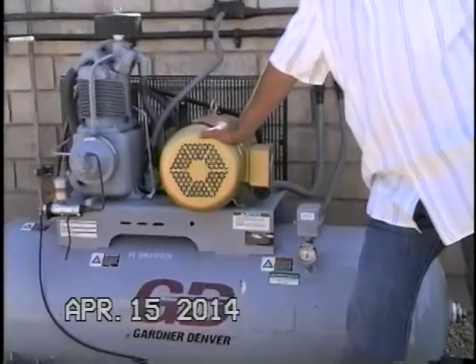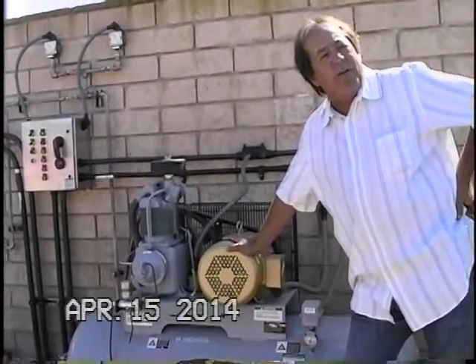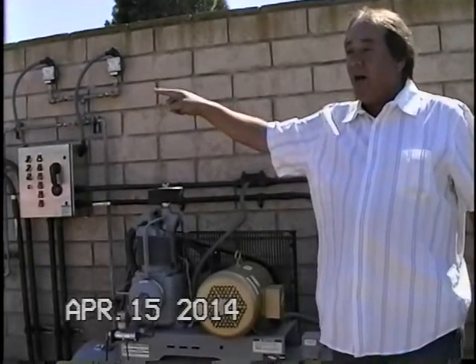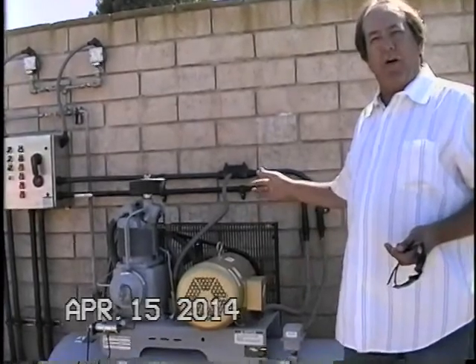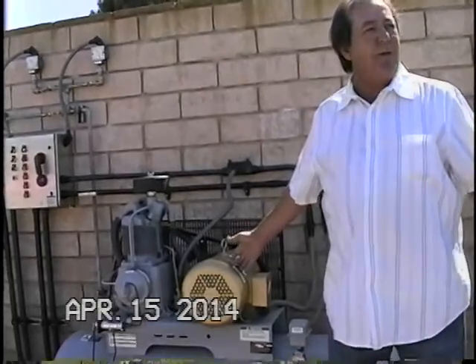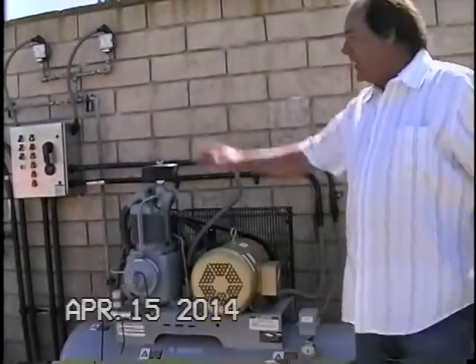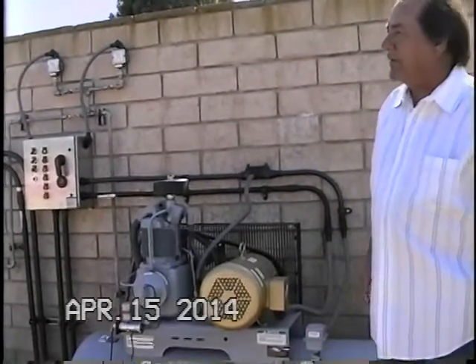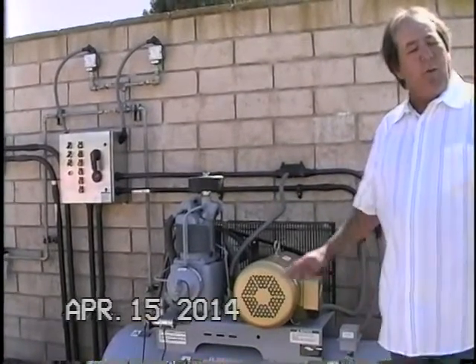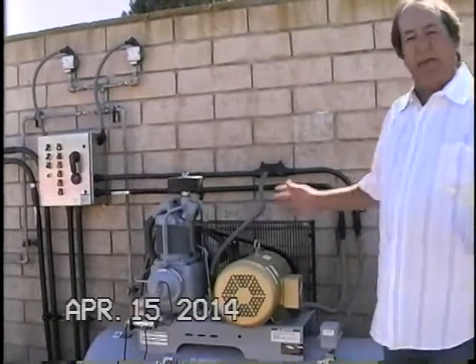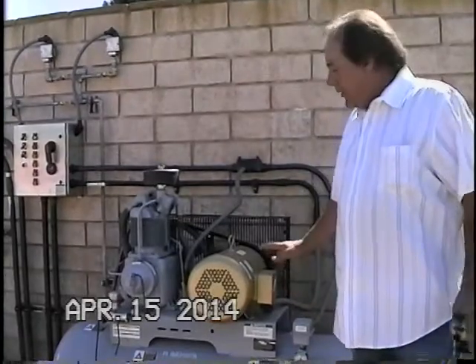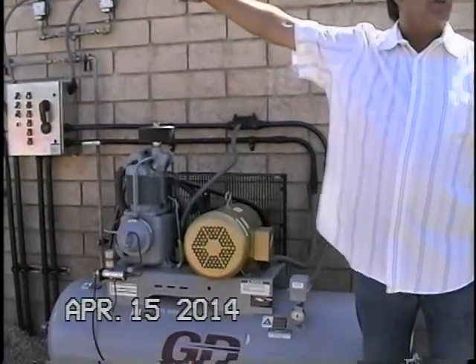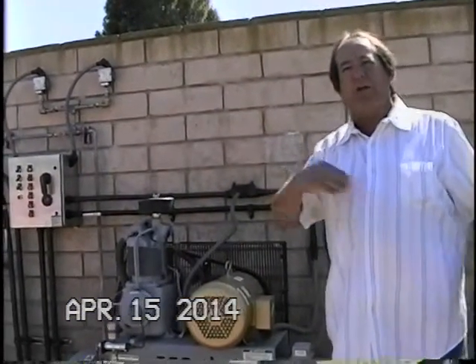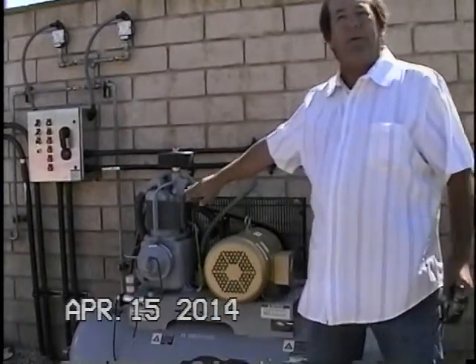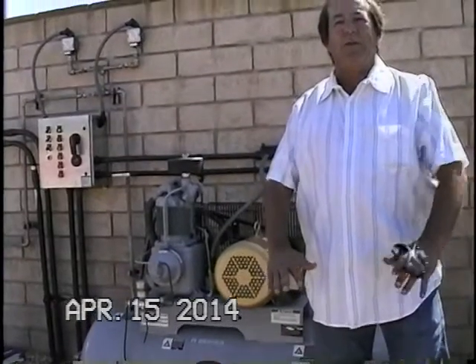So you always have to set your pressure settings higher than the maximum pressure that you would ever see in any standard operating condition of the surge tank. Because if the pressure setting wasn't high enough and we had a call for air, then the compressor wouldn't ever turn on. Even though the tank pressure right now, I don't know where it's at, about 120, and we're at 160, what happens when we have a call for air, immediately within, I'd say, 10 or 15 seconds, this air compressor will equal the pressure inside the tank. So that higher pressure gets drained into the tank, and then this just becomes a pump. And it's just pumping air volume in there and pushing that liquid level down, as we explained earlier.